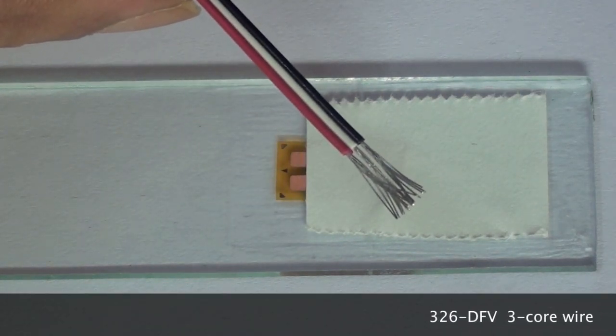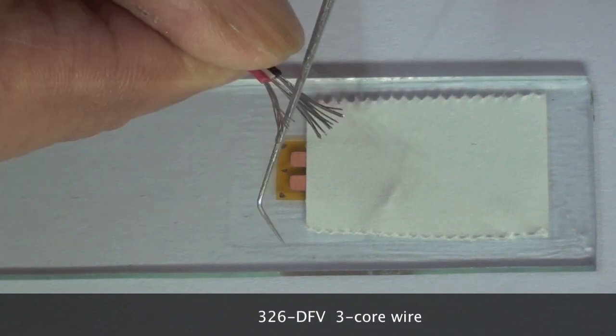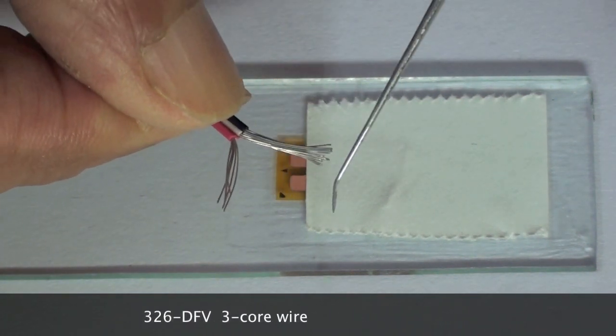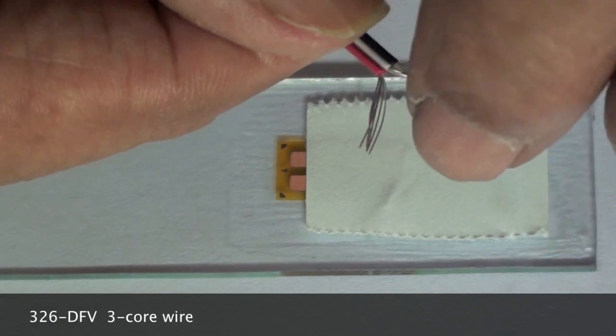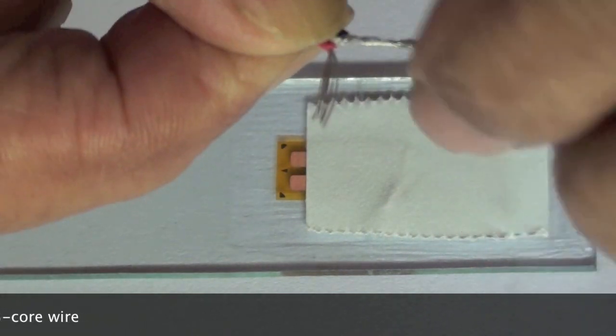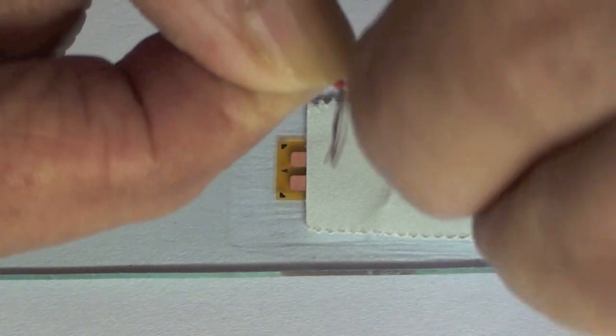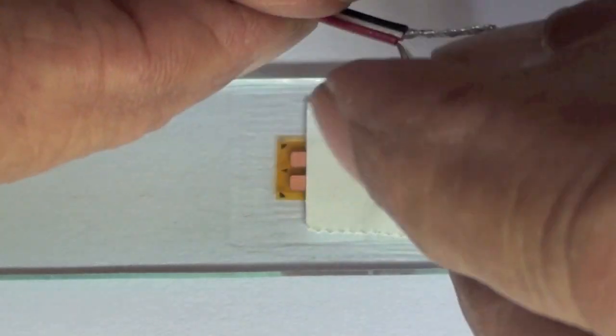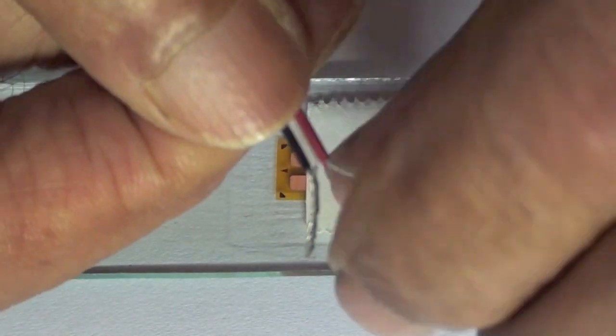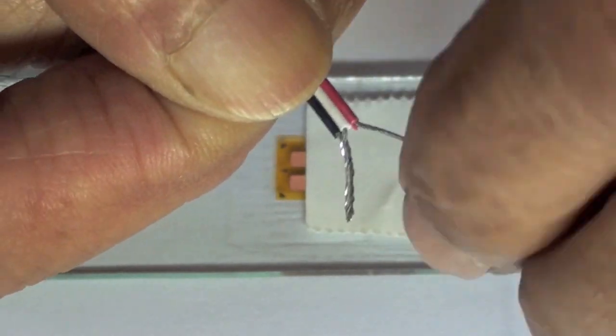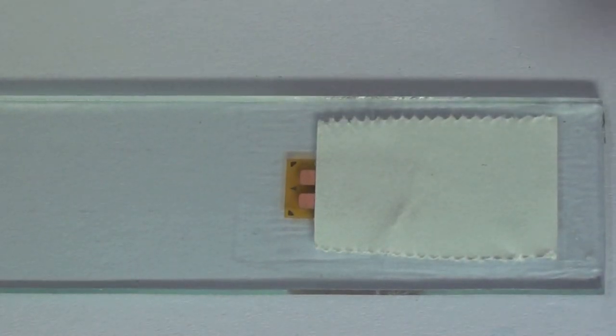For single element strain gauges, a 3 lead wire connection is used to connect the gauge to an instrument as a quarter bridge. The conductors of one lead wire are separated from the other two and the conductors are twisted tightly until the twist extends all the way to the insulation.